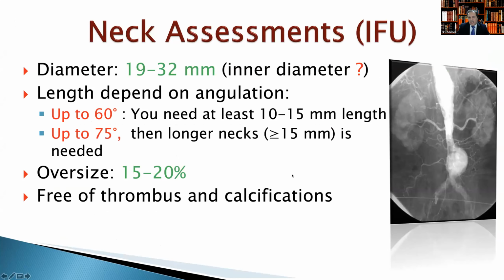If you look at the IFU, all of us know that the diameter of the neck should be between 19 to 32. For the length of the neck, if the angulation is up to 60 degrees, we need at least 10 to 15 millimeter of neck. If it's up to 75, then we need more than 15 millimeter. This is the IFU.